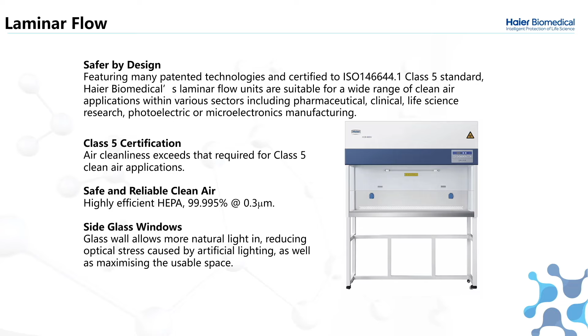Laminar flows have a very niche application. They do not provide any operator protection. However, they reduce the cost of working, as the unit is cheaper compared to a biological safety cabinet.